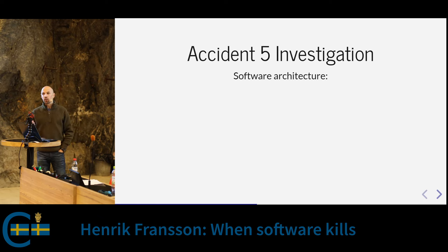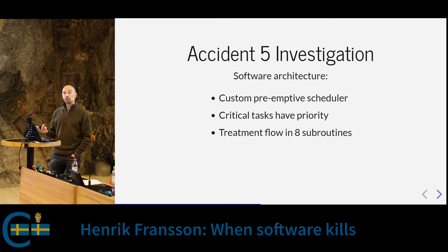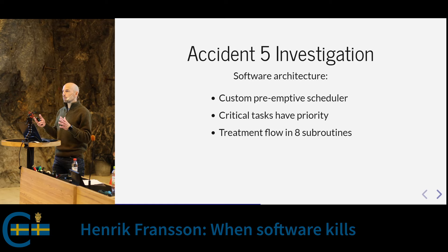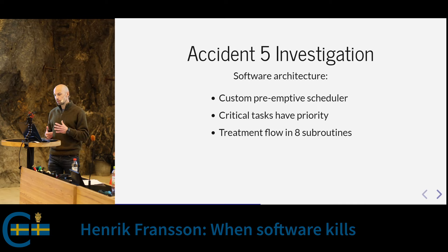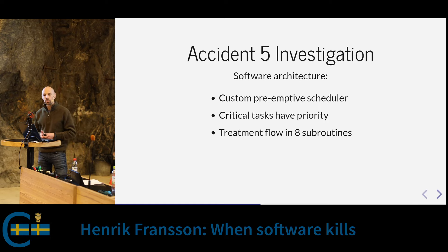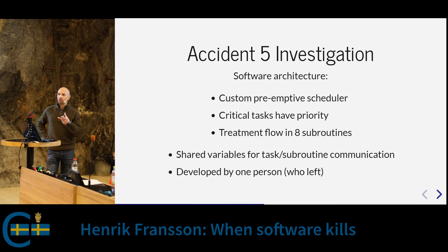To understand the potential race condition, we need to look at the software architecture. They had made their own little operating system or scheduler with tasks of different priorities and eight subroutines handling all the treatment-related functions. The scheduler ran every 100 milliseconds checking for higher-priority tasks, and also received keyboard and other interrupts. They used shared variables for communication between tasks and subroutines — and I think you can figure out where this is going.